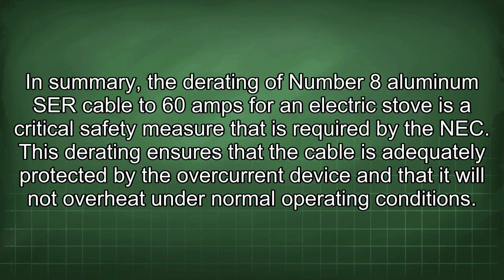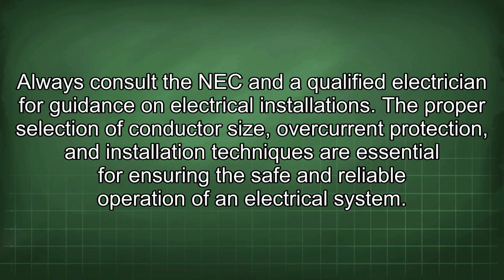In summary, the derating of number 8 aluminum SER cable to 60 amps for an electric stove is a critical safety measure that is required by the NEC. This derating ensures that the cable is adequately protected by the overcurrent device and that it will not overheat under normal operating conditions. Always consult the NEC and a qualified electrician for guidance on electrical installations.